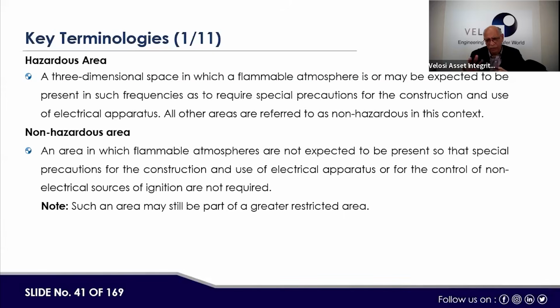Now, as we have spent some time, at least we should know certain terminologies which we use during the HAC process. Number one, hazardous area: a three-dimensional space in which a flammable atmosphere is, or may be expected to be, present in such a frequency as to require special precautions for the construction and use of electrical apparatus. All other areas are referred to as non-hazardous in this context. Then non-hazardous area: a three-dimensional space where no hydrocarbon, flammable material or dust is present. That is normally called a non-hazardous area. Like we say process area and utility area. In the utility area, except the fuel gas area where hydrocarbons are available, if you take fire water, nitrogen, or other utilities, then those are normally called non-hazardous areas.